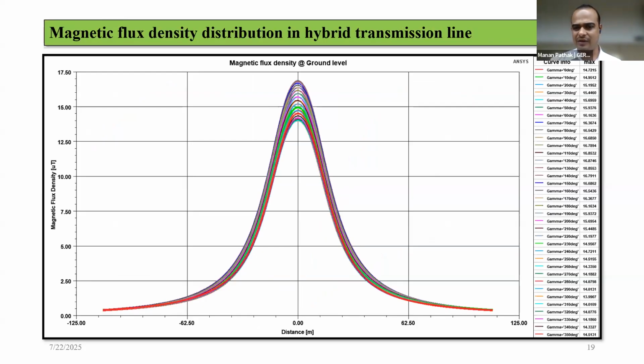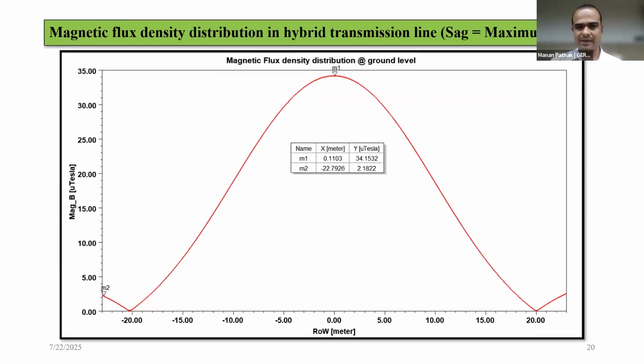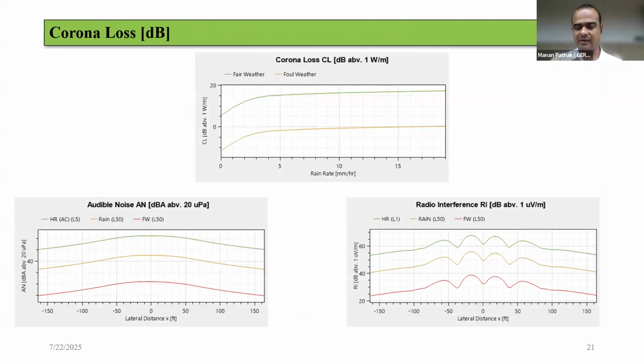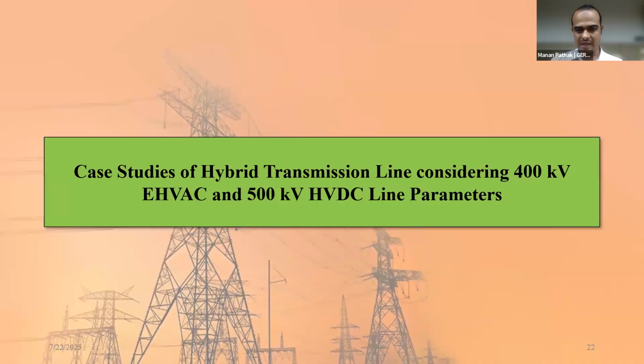Subsequently, the magnetic field is of little concern, because the magnetic field limit as per the guideline is 100 microtesla, and we are getting results within 17. So it will not be a big concern as far as the hybrid line is considered. And again, the side effects of corona, that is radio interference and audible noise. As far as our result is concerned, the simulation that we secured in line with the trial and error method, the mathematical calculations and the optimization algorithms, all results are very fruitful and within range as per the Ministry of Power guidelines and as per the CEA authority.